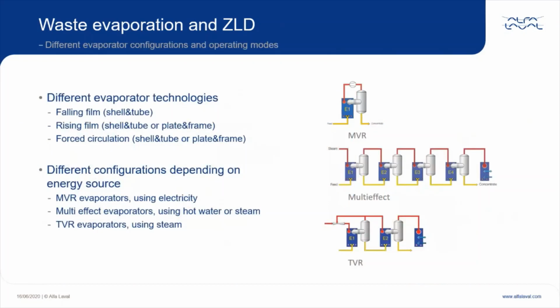And there are several different evaporation technologies and configurations available in the market, both based on traditional shell and tube technology and based on gasketed plate and frame evaporators. In some evaporators, the vaporization process, that is the boiling, happens at the heat transfer surface, which is okay for clean applications. For the more demanding duties, for example, if there is high viscosity or high scaling potential, which is the case for most wastewater application and crystallizers, the so-called forced circulation and flashing evaporators should be used instead.